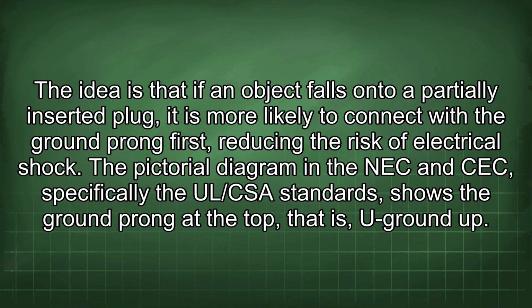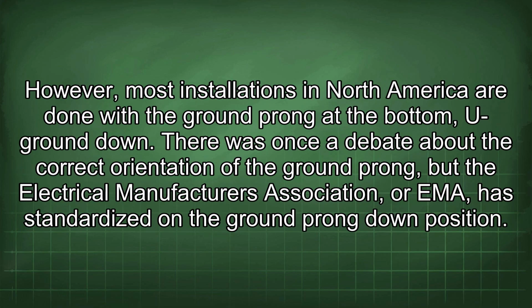The pictorial diagram in the NEC and CEC, specifically the UL/CSA standards, shows the ground prong at the top, that is, U ground up. However, most installations in North America are done with the ground prong at the bottom, U ground down. There was once a debate about the correct orientation of the ground prong, but the Electrical Manufacturers Association, or EMA, has standardized on the ground prong down position.